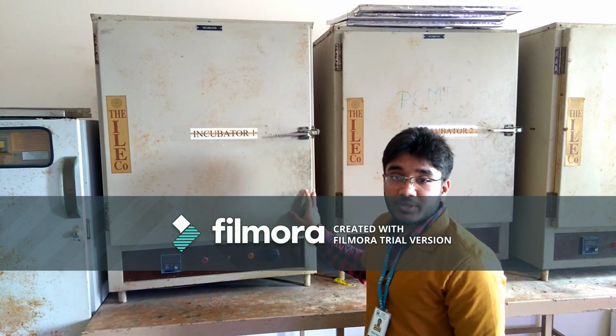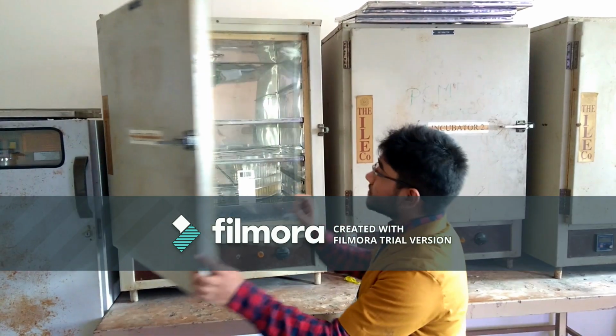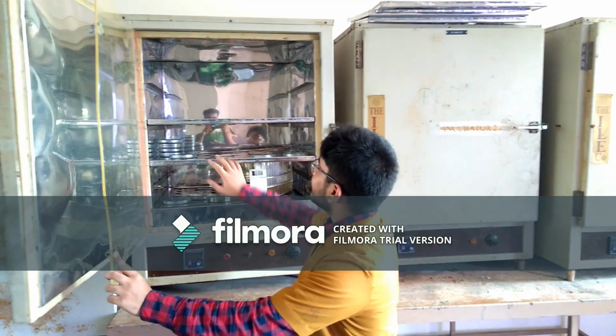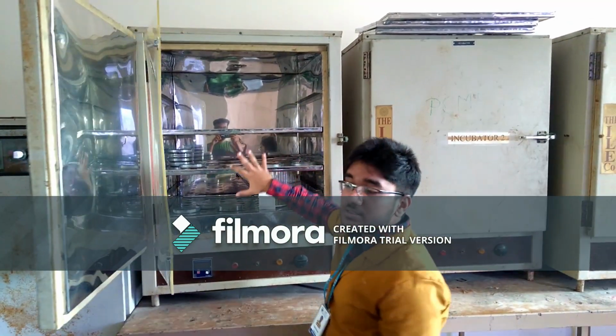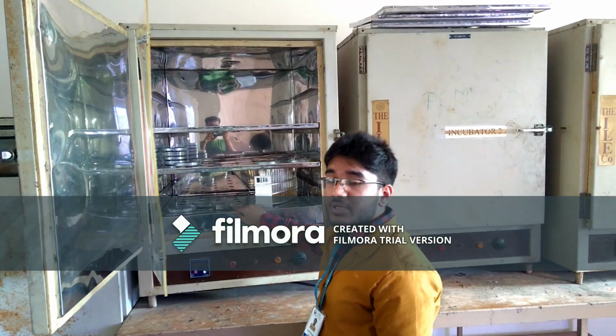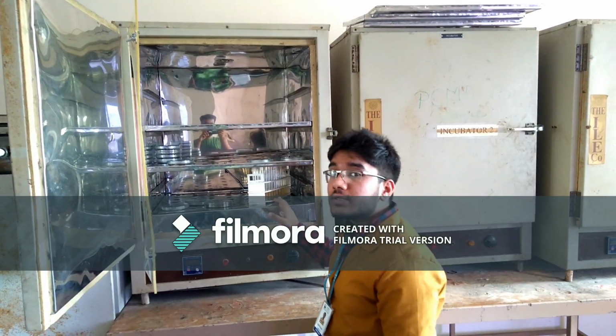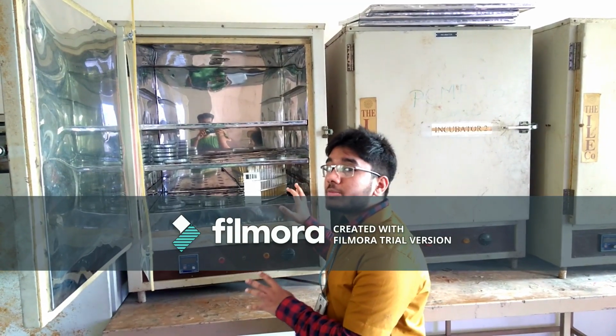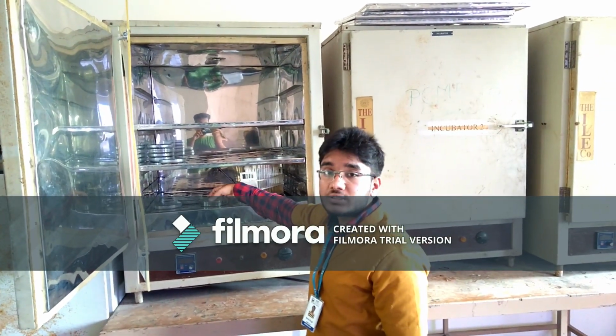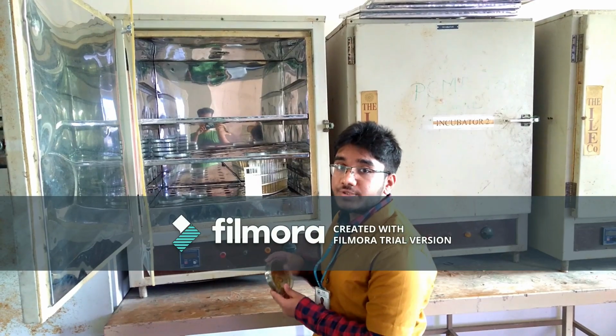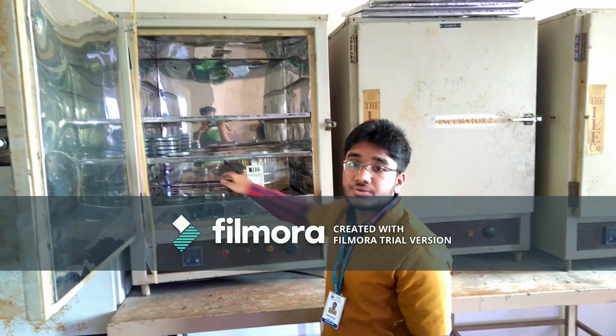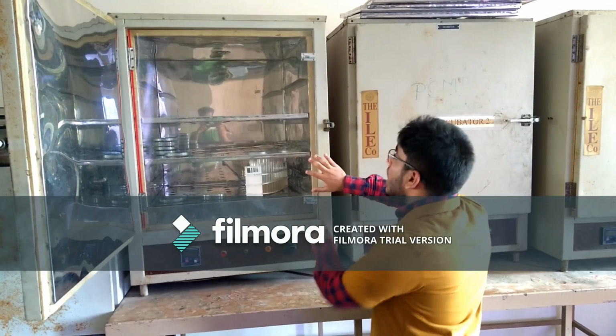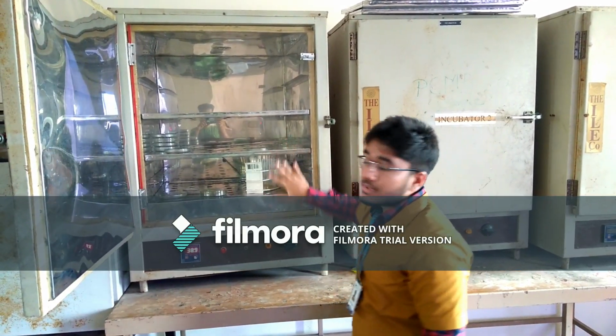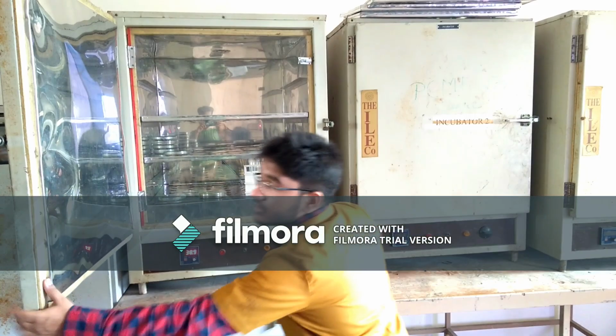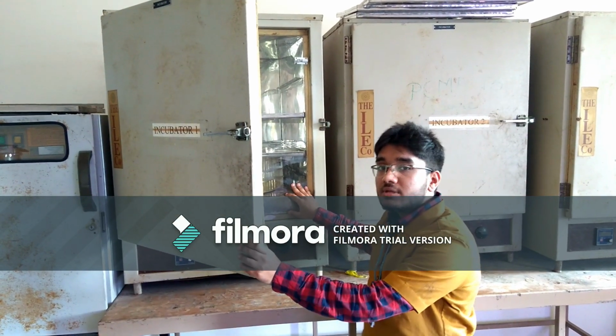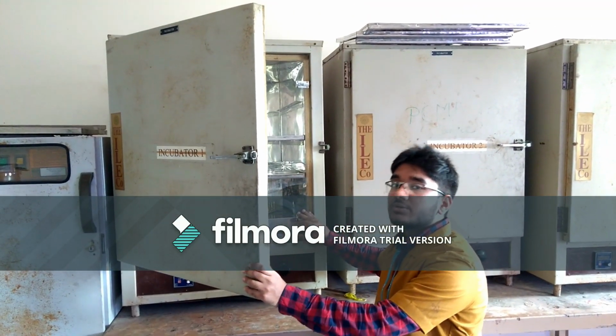This is a simple incubator. When we open it up, we see that it is covered by the 5 layers of the incubator. It is covered by insulated material which doesn't allow the heat to enter or exit the incubator, so that the microbial cultures which are stored in it can be preserved and can be used as a growth medium. In addition to these layers, there is also a plastic layer, and with this, there is a solid thick layer. It acts as an insulator and doesn't allow the heat to enter or escape.